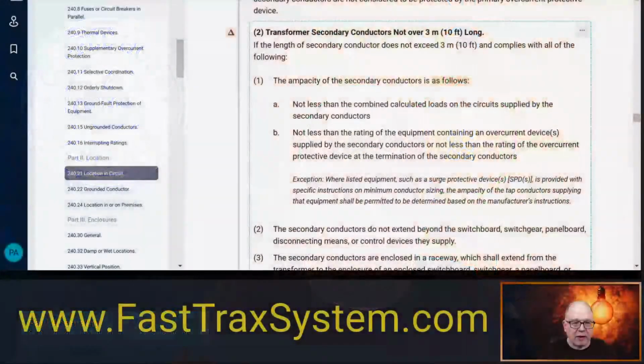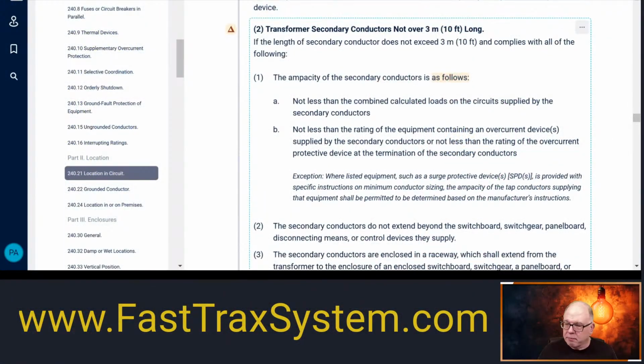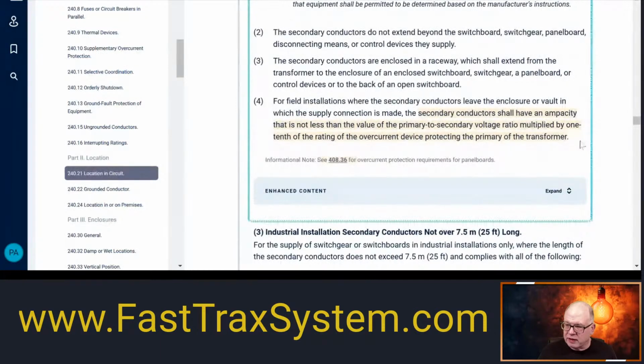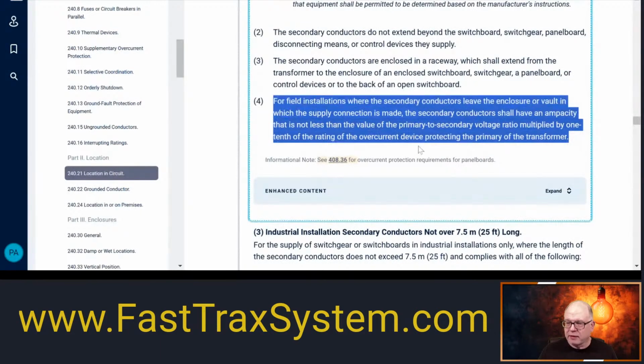The only time that this may not be the case is if we're dealing with a small transformer, a 25 kVA transformer or something smaller, where the conductors may calculate out to a certain size based on the rules up here. But ultimately, you still have to make sure that it's at least sized what? The primary to secondary voltage ratio multiplied by 1/10 of the rating of the overcurrent device that's actually protecting the primary.